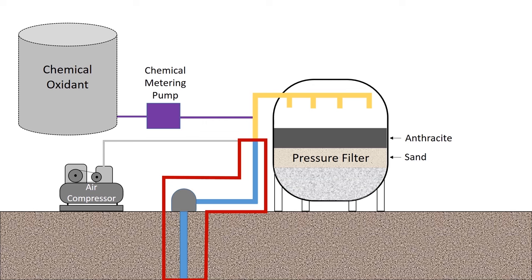But if we don't deal with these high concentrations of iron and manganese, when they do become oxidized, such as when they come out and are oxidized by the air in a glass in the customer's home or in a sink or in the bathtub, the exposure of the iron and manganese in the water to the oxygen in the air will cause it to oxidize and then come out of solution and change colors.